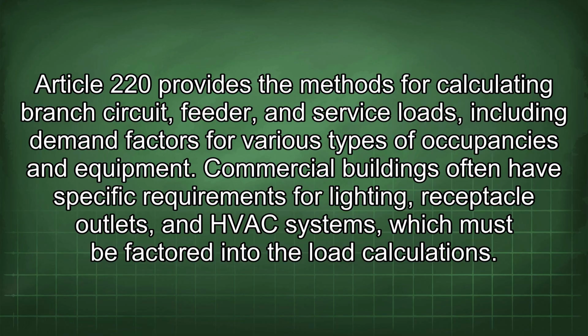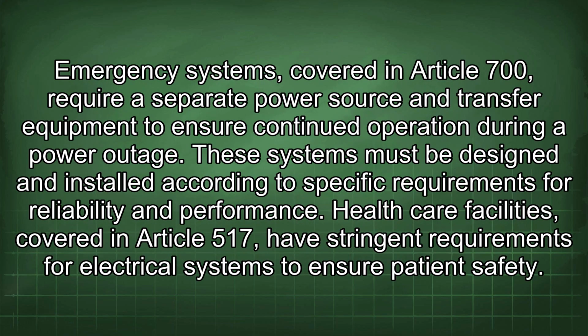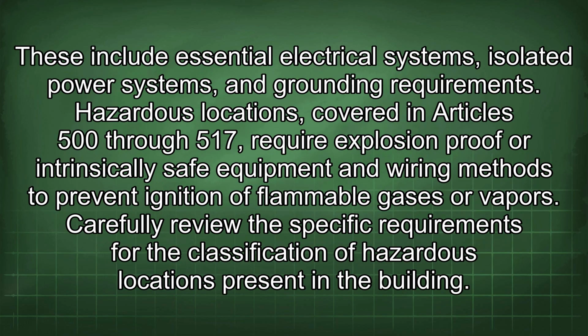Commercial buildings often have specific requirements for lighting, receptacle outlets, and HVAC systems, which must be factored into the load calculations. Emergency systems, covered in Article 700, require a separate power source and transfer equipment to ensure continued operation during a power outage. These systems must be designed and installed according to specific requirements for reliability and performance. Healthcare facilities, covered in Article 517, have stringent requirements for electrical systems to ensure patient safety. These include essential electrical systems, isolated power systems, and grounding requirements.